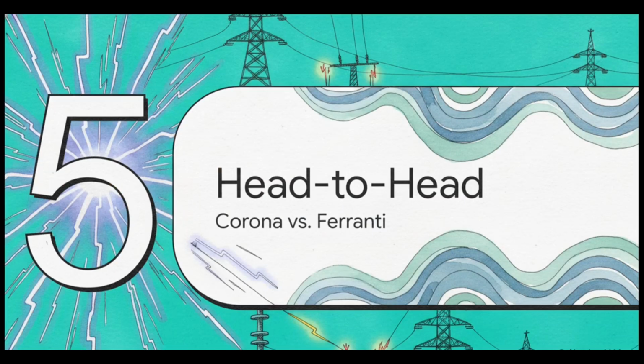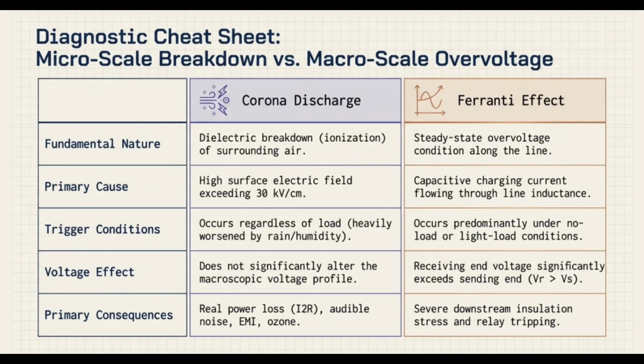All right, Section 5, the high voltage head-to-head. Corona versus Ferranti. Let's put these two side by side to really lock this in. Let's look at the core differences. By nature, corona is a dielectric breakdown of the air, while Ferranti is a steady-state overvoltage condition. The cause? Corona is driven by a high surface electric field gradient, but Ferranti is driven by capacitive charging currents. Now, consider the conditions. This is interesting. Corona happens regardless of load, but it's heavily worsened by foul weather, like rain and high humidity. Ferranti, on the other hand, is triggered by a lack of power demand. It happens mostly under no load or light load conditions. Corona doesn't really alter the overall macroscopic voltage profile, but it does cause real power loss, noise, and that corrosive ozone. Ferranti does alter the voltage, massively stressing downstream insulation because the receiving end voltage becomes greater than the sending end. Basically, one bleeds power, the other forcefully pushes too much.